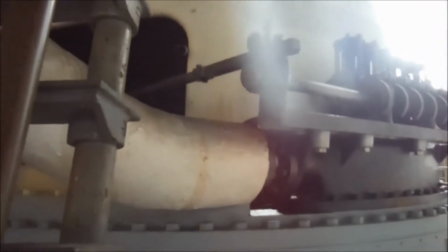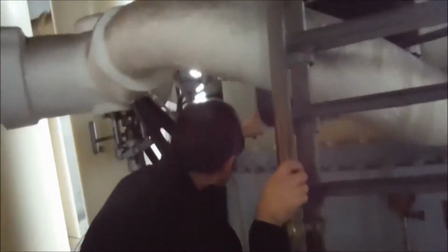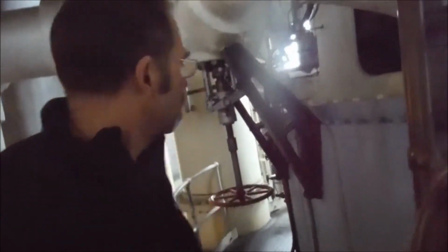Same thing's happening here with the rack and pinion gear. So that rack and that pinion will work those poppet valves for steam admission to the turbine, and that whole assembly is controlled by a governor arm that comes down from the top and works all this governor linkage inside here. And what you're looking at in there is the shaft, turbine, generator. That's the power transmission shaft up into the generator, and this is your steam admission valve and probably an emergency hand trip painted red. In case of oh shit.